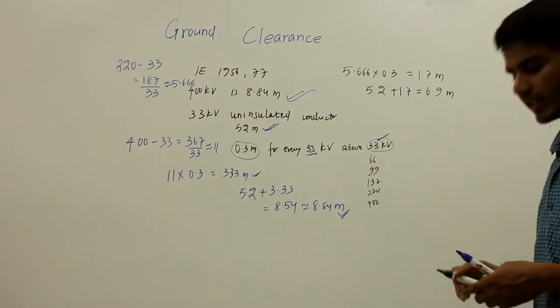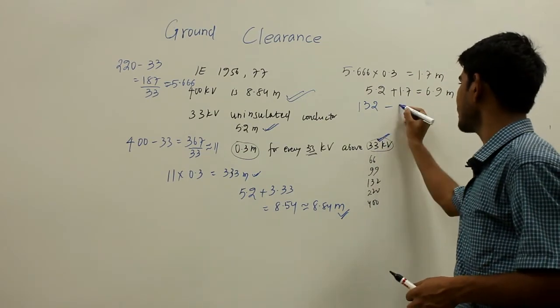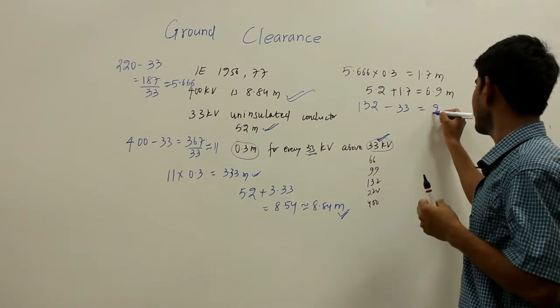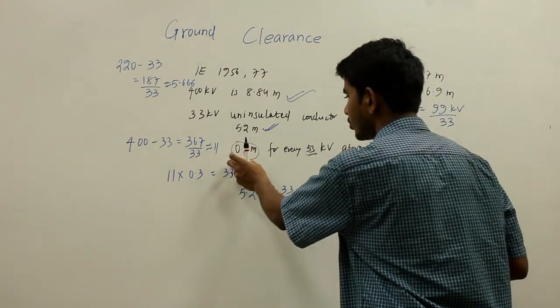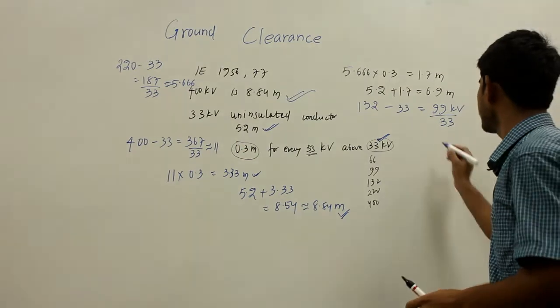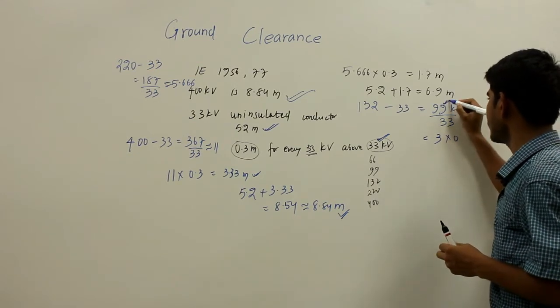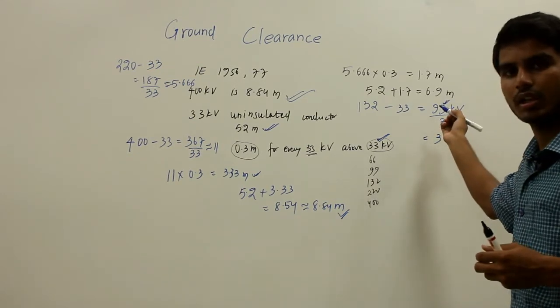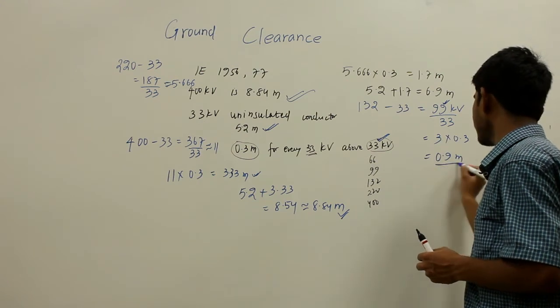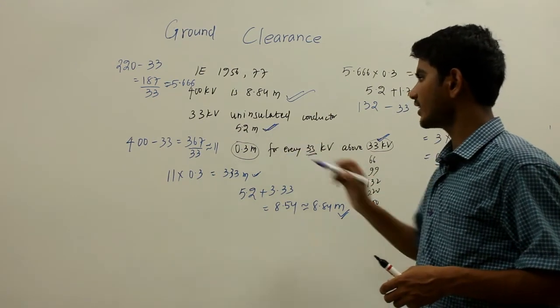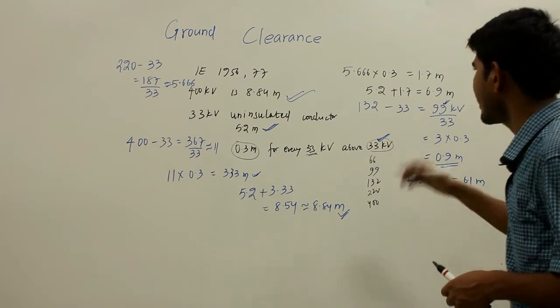Similarly, let us find the minimum ground clearance for a 132 kV line. Subtracting 33 kV gives 99 kV. Dividing 99 by 33 gives 3. So 3 times 0.3 equals 0.9 meters. Adding 0.9 meters to the base clearance of 5.2 meters gives 6.1 meters.